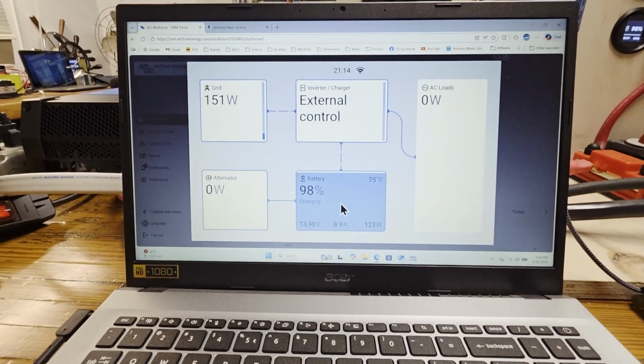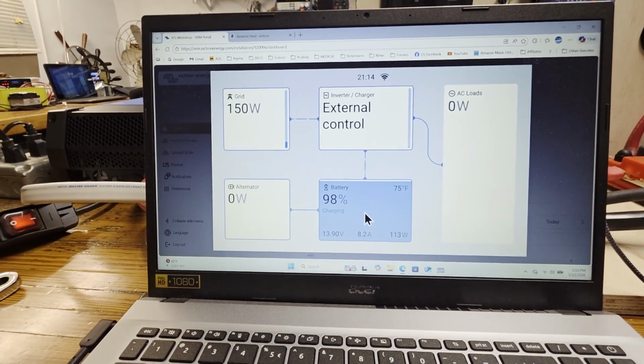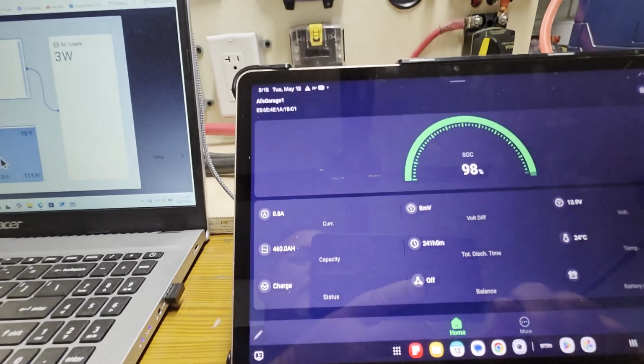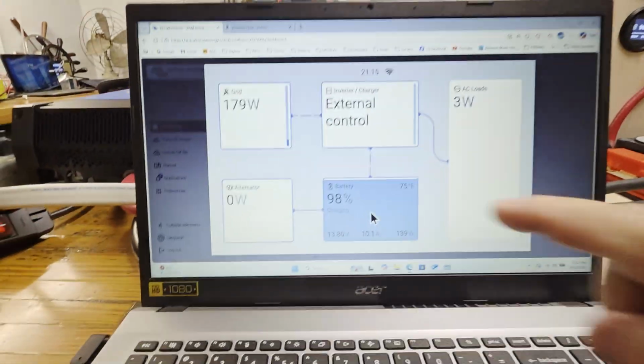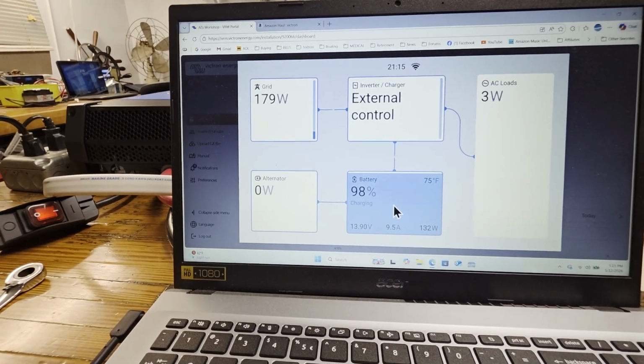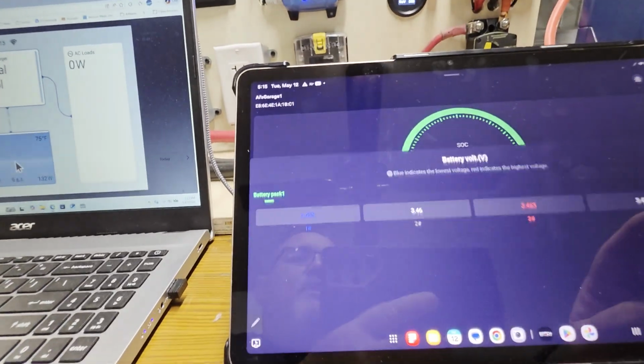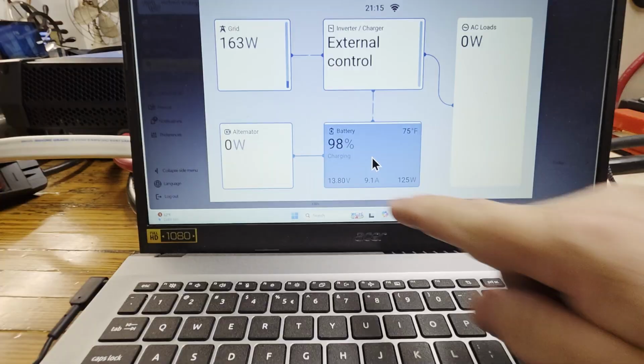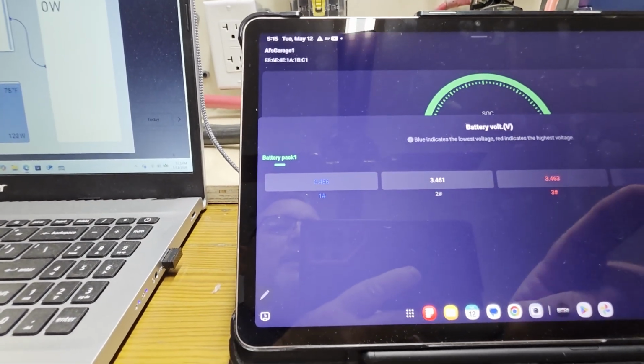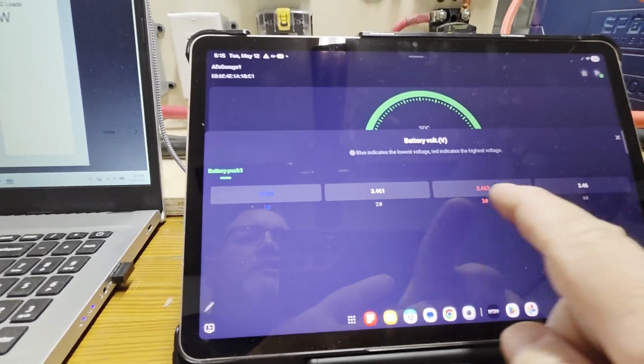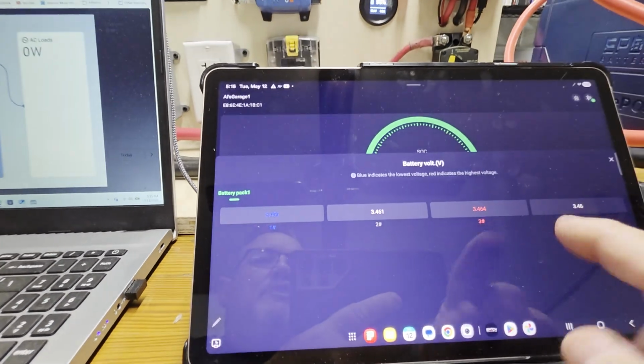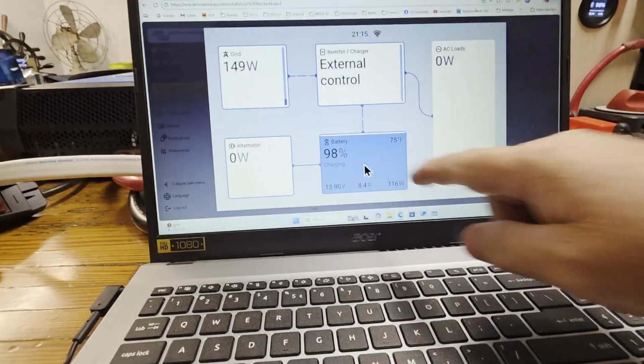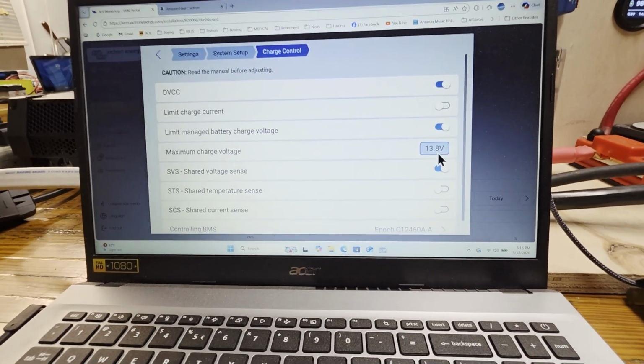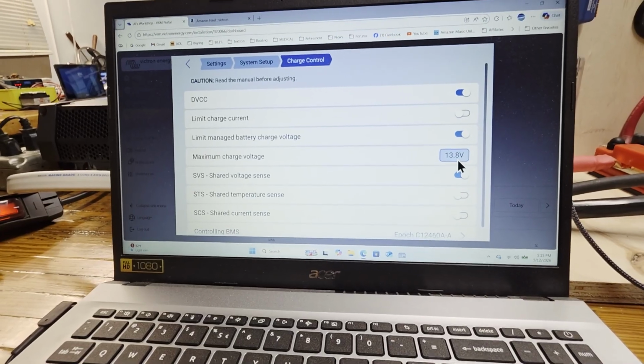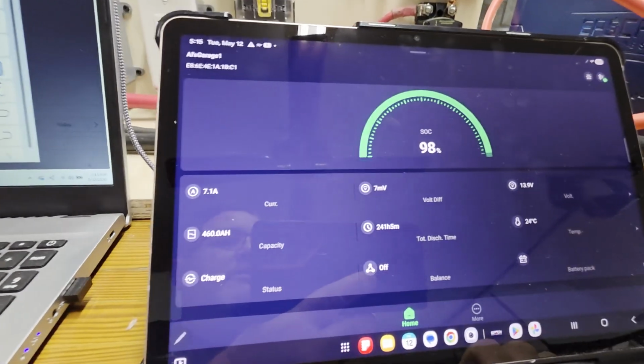One other thing: if you start at 13.8 as programmed into the DVCC or limit charge voltage, and you happen to get the cell overvolt warning, then you need to start over. You need to discharge the battery slightly, lower it to 13.7, and start again, because we are just trying to get the maximum voltage set in here to start the balance procedure without getting one of these cells to overvolt. So if one of these cells overvolts, just do a little bit of discharging until the cell overvolt warning clears, then reconfigure your DVCC voltage to 13.7, start again, and let it sit at 13.7 until you get the cell delta of 50 or less.